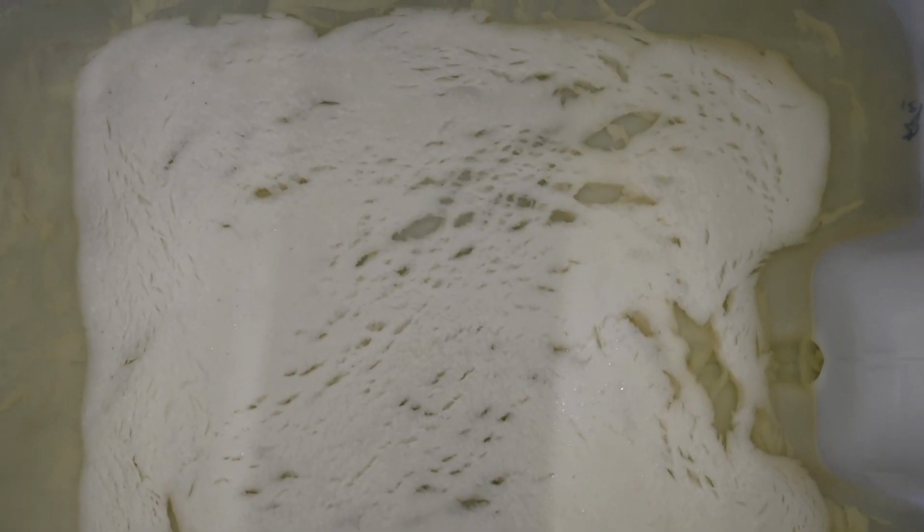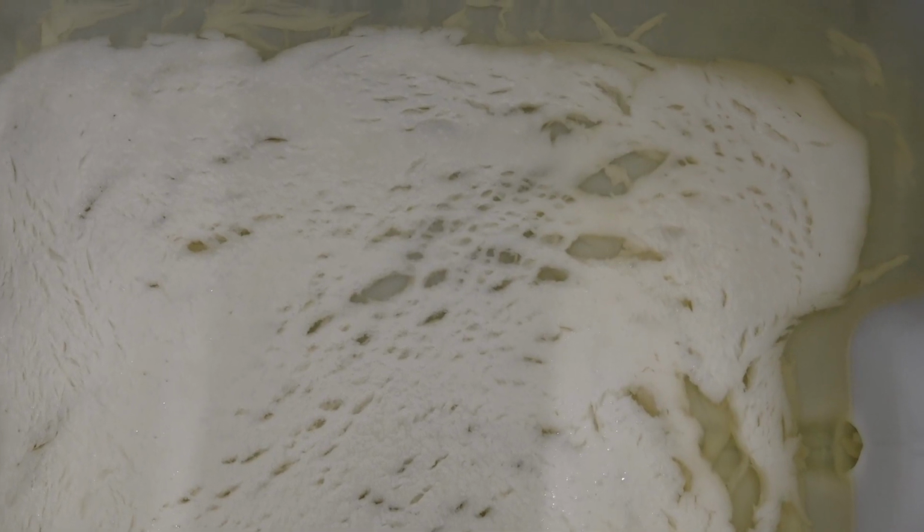And then we checked and tested the foam concentrate in the other engines and the foam concentrate that we still had in stock. That doubled the amount of the foam concentrate that was affected. And then we talked to other fire departments that have the same foam concentrate from the same manufacturer. So we ended up with over 40,000 liters of foam concentrate in which there was a phase separation or in which the extinguishing performance was significantly worse than usual.